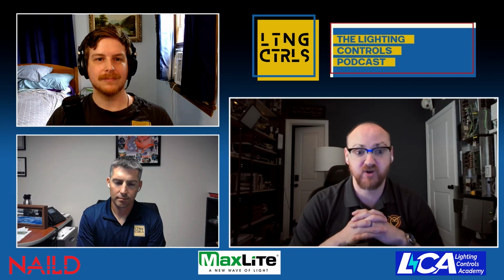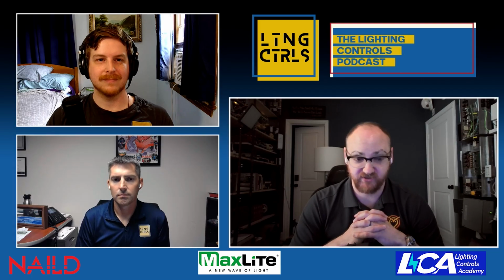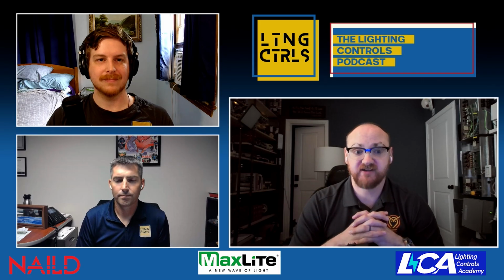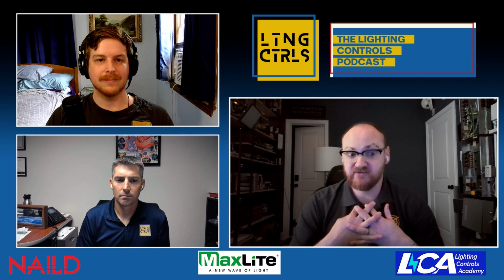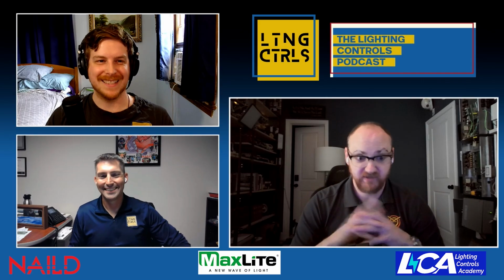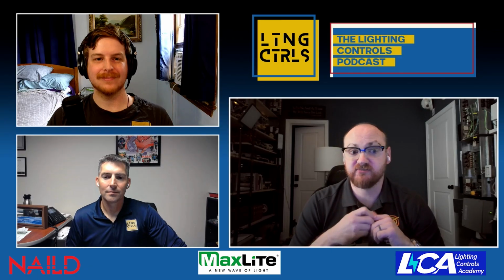Exactly, that's the role of the commissioning advisor, so mine is to verify system functionality has been programmed the way it's supposed to. I'll check about 10%, making sure that's functioning as expected. If I've programmed anything special or out of the ordinary, I'll check that too. But other than that, I rely on the commissioning agent, who's paid to check roughly 30% or more per their contract, to tell me if there are discrepancies I need to look at. At that point it means I was lied to, and somebody's been flipping dip switches or turning dials they shouldn't have, because for the most part, depending on the manufacturer I'm working under, it's not my job to mess with the analog devices. I only mess with the digital devices on most projects.